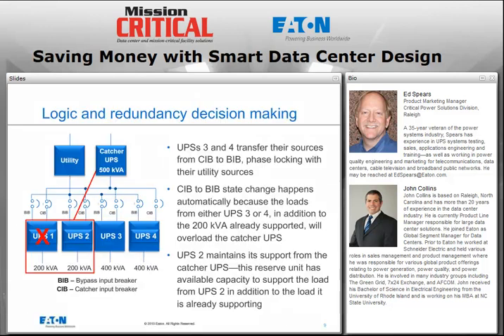Basically, the smart catcher system is looking at the loads on the output of the UPSs and setting up what I'll informally call a club. In other words, UPS 1 and UPS 2 are in the club right now because the catcher UPS can handle them. On the other hand, let's say that UPS 3 were to fail and UPSs 1 and 2 were still okay along with UPS 4. Then UPS 3 would be in the club and no one else would be, because the catcher system's only rated at 500 kVA. So the breakers up above the UPSs, the CIB, the catcher input breakers and the bypass input breakers, automatically under redundant controls will operate to determine who is supported by the catcher, up to and including the full capacity of the catcher, and thus who is supported by straight utility bypass.